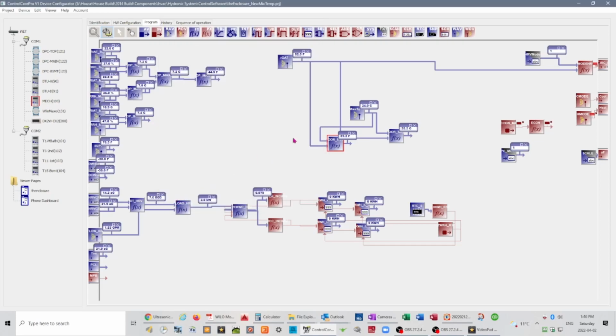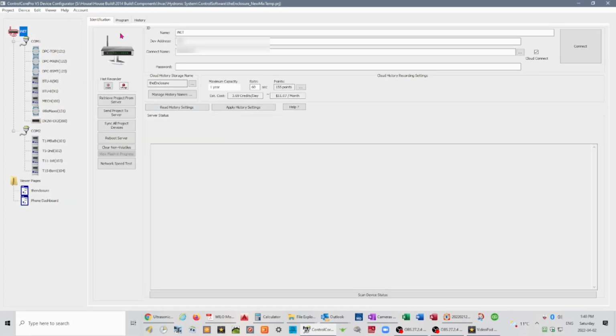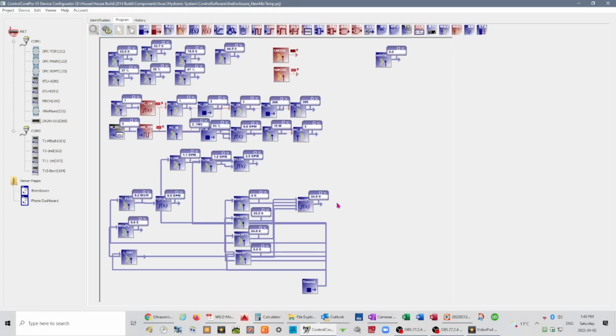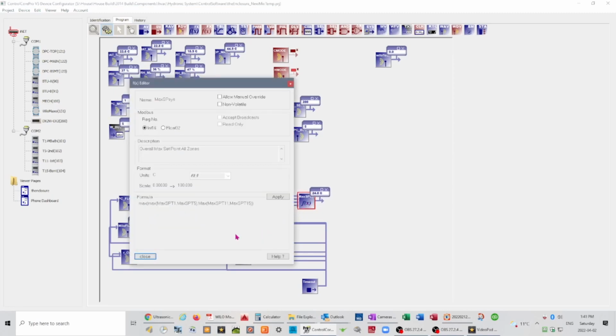To get the maximum temperatures, I start with the iNet. That is the variable or the block that I'm calling, and it's just saying max, max, max. Now, one of the things I didn't necessarily like about the programming in this control core is its max command only allows for 2 variables instead of unlimited variables. So that's why you have these nested maxes, which is kind of a pain in the butt, but if that's the worst of it, then that's not too bad.